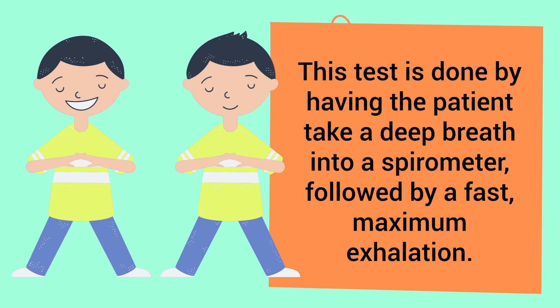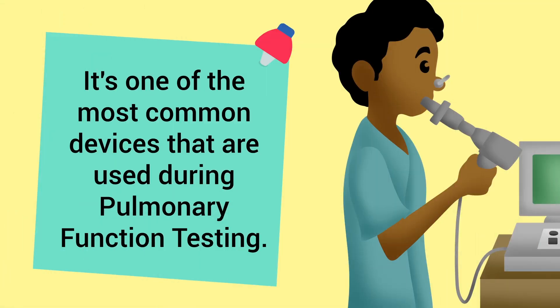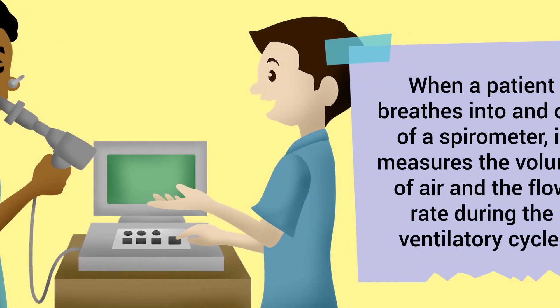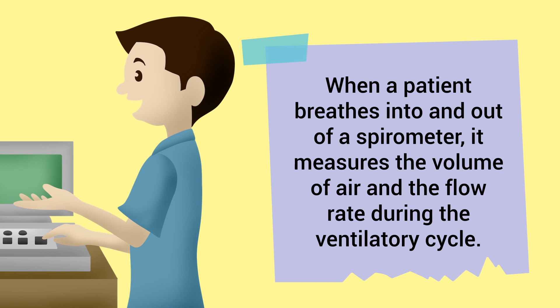The test is followed by a fast, maximum exhalation. A spirometer is one of the most common devices used during pulmonary function testing. When a patient breathes into and out of a spirometer, it measures the volume of air and the flow rate.